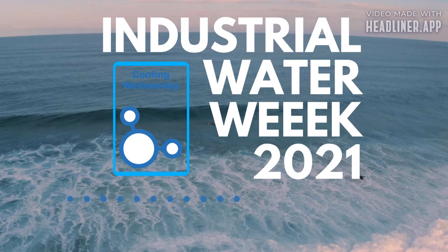The way I really prefer feeding cooling towers is based on demand. And there's two ways to do that. There's how much water is coming into the system, and that is my favorite way to do that. If we lose water for any reason, our controller is going to know about it, and then it is going to pump the proper amount of product to replenish whatever was lost. So that means if we have a leak, if we're bleeding the system, however we lose water, we're going to see it via our controller, and the right amount of our inhibitor is going into the system.